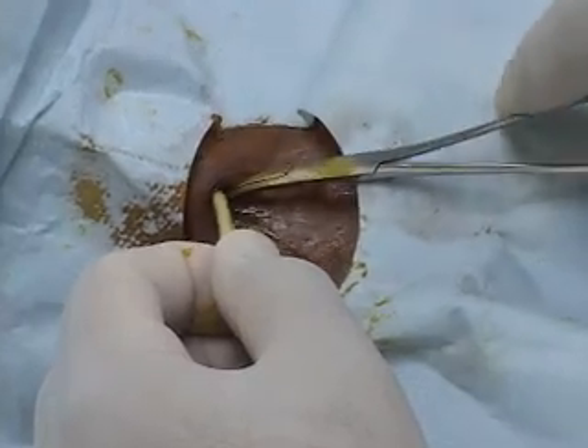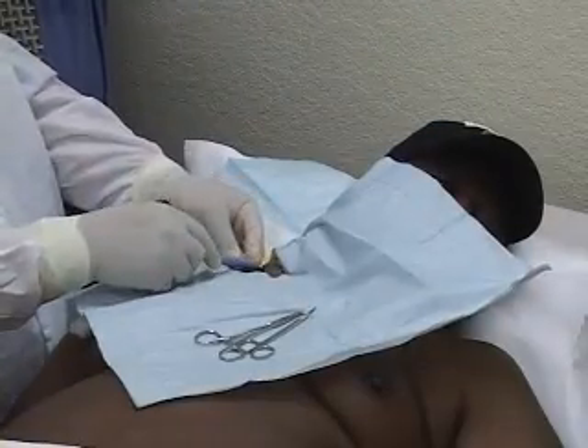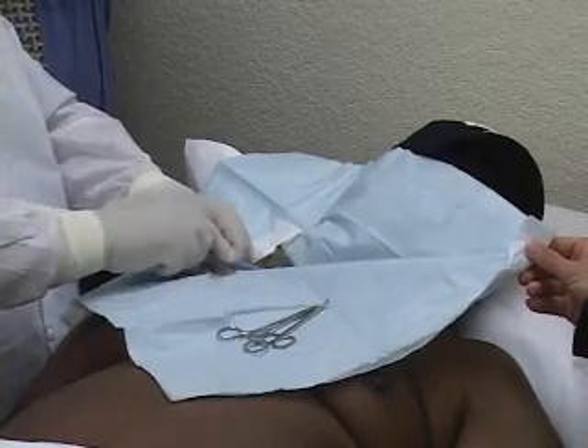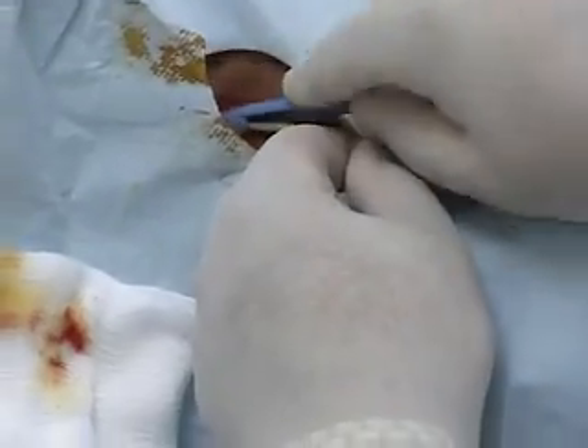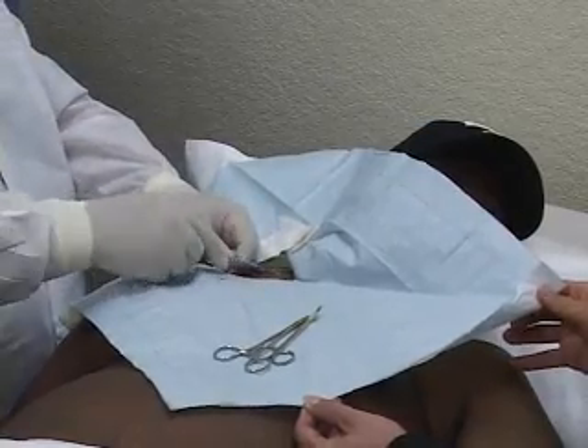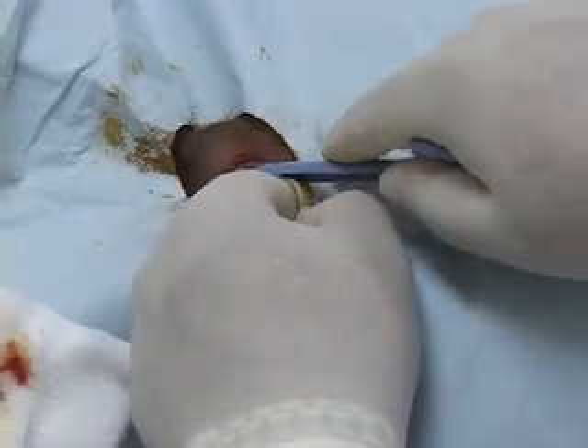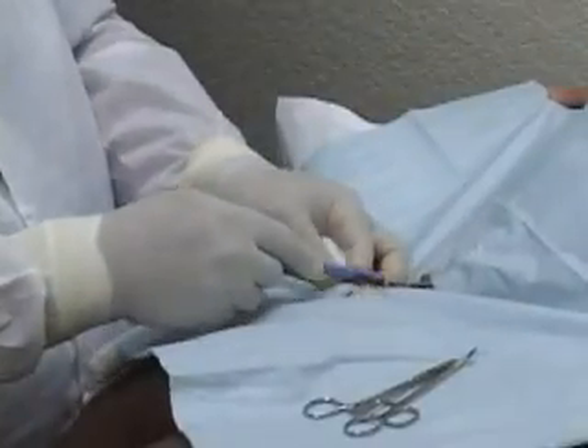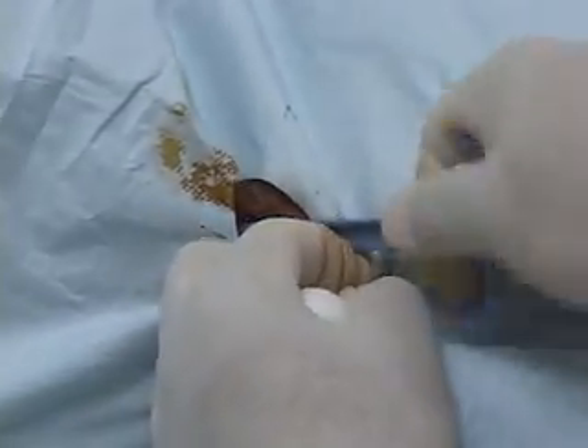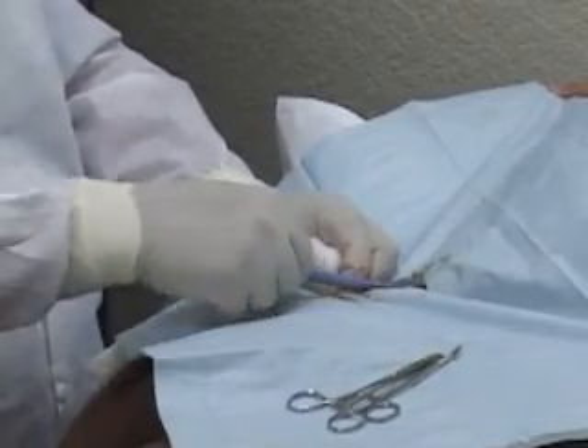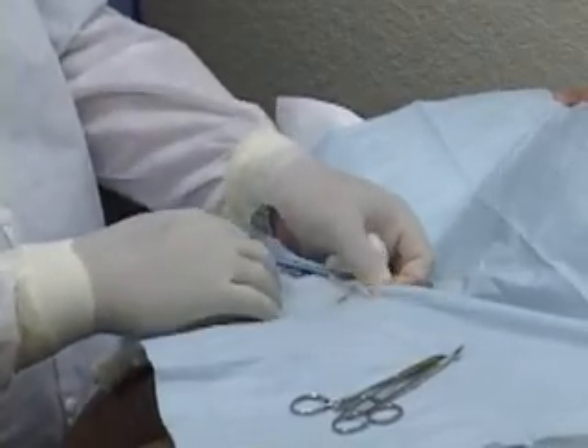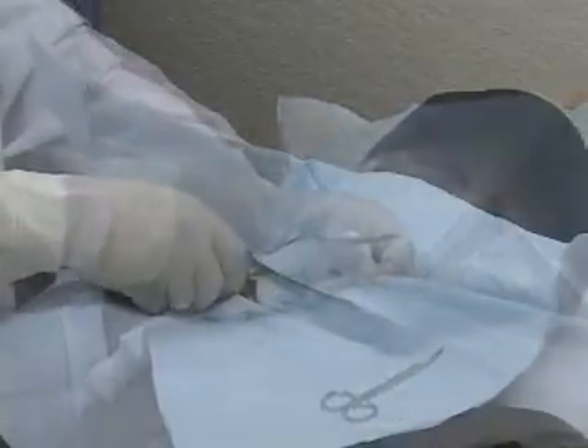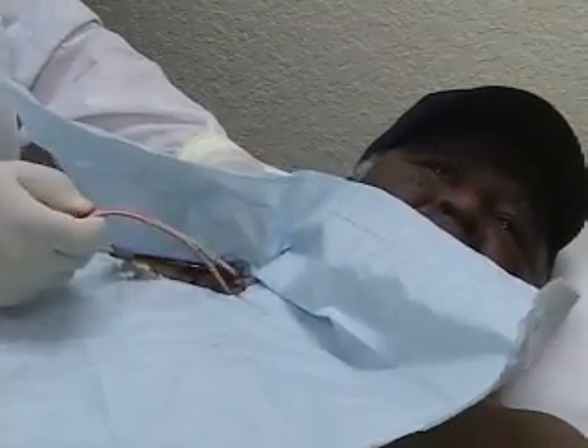Using the hemostat included, expand the exit site. Insert the extractor through the slit opening over the exposed catheter. Hold the extractor at the T-handle and with a twisting motion, insert the head of the extractor through the opening. If having difficulty getting under the opening, please use a mosquito hemostat again to expand the opening. Then manipulate the extractor in and out of the opening, noticing the head of the extractor going into the tunnel further and further. With the other hand, hold on to the exposed catheter, pulling at the same time the extractor is inserted. Once through the cuff, the catheter should come out with ease.